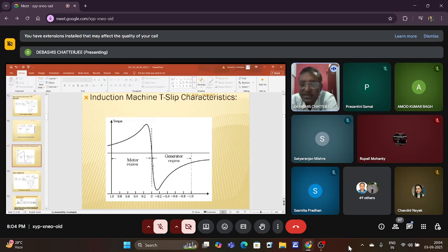Now this generator has some rated slip. So this is the rated slip, which usually tends to be around 4%, 4.5%, 3.5% like that. So take an average of 4%. So 4% rated slip is actually 60 RPM. So at 1560 RPM, this generator is supposed to generate rated power.